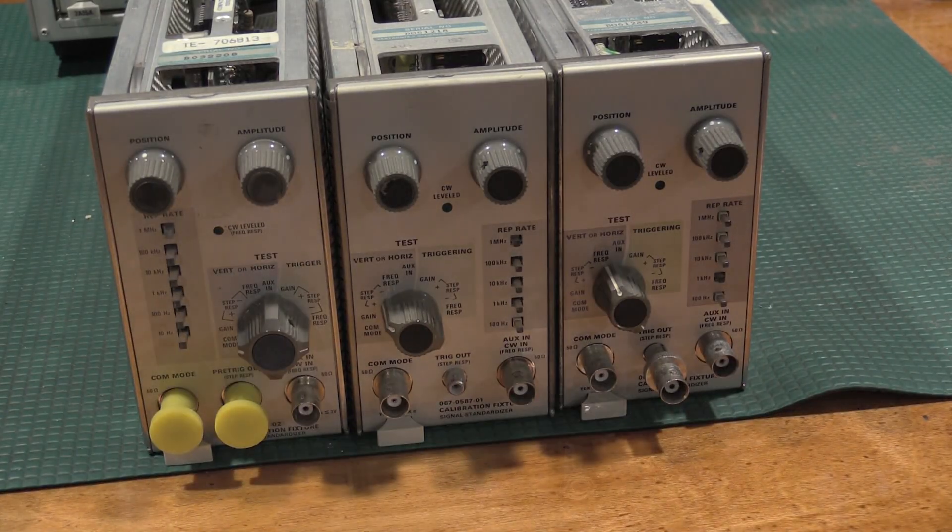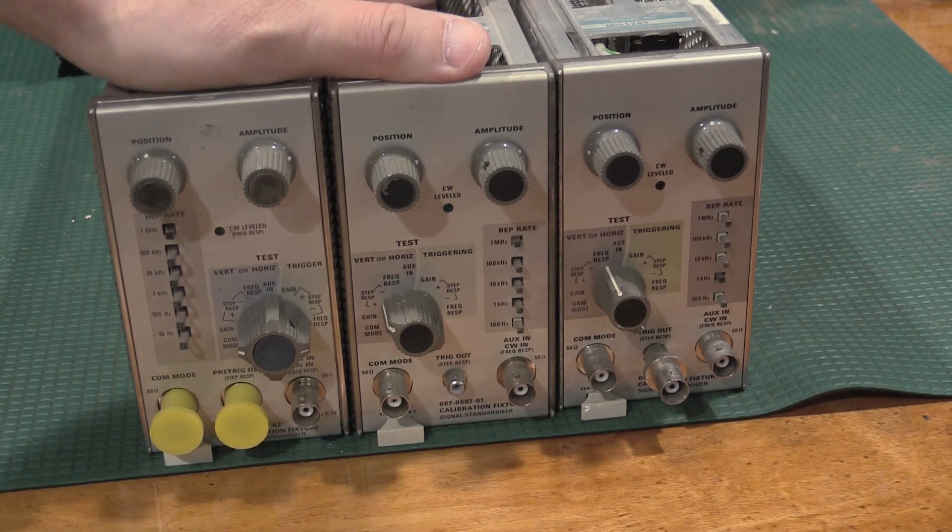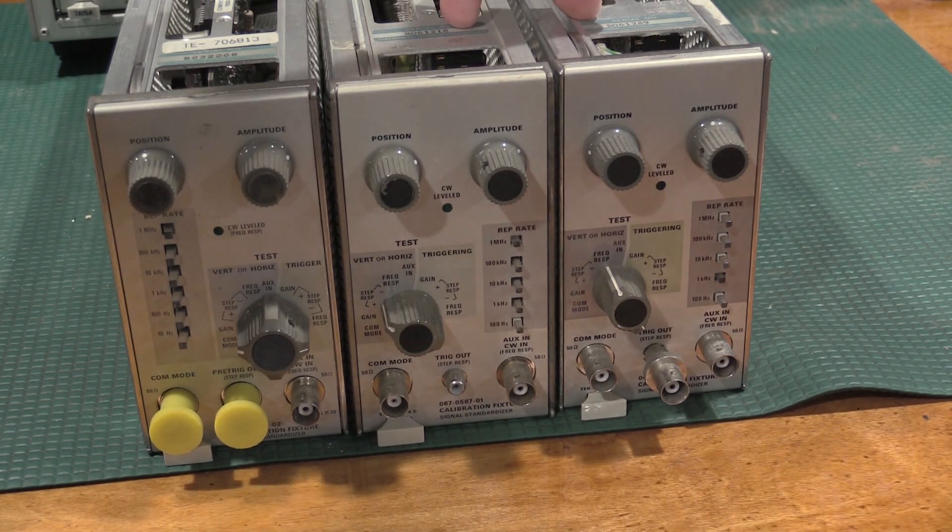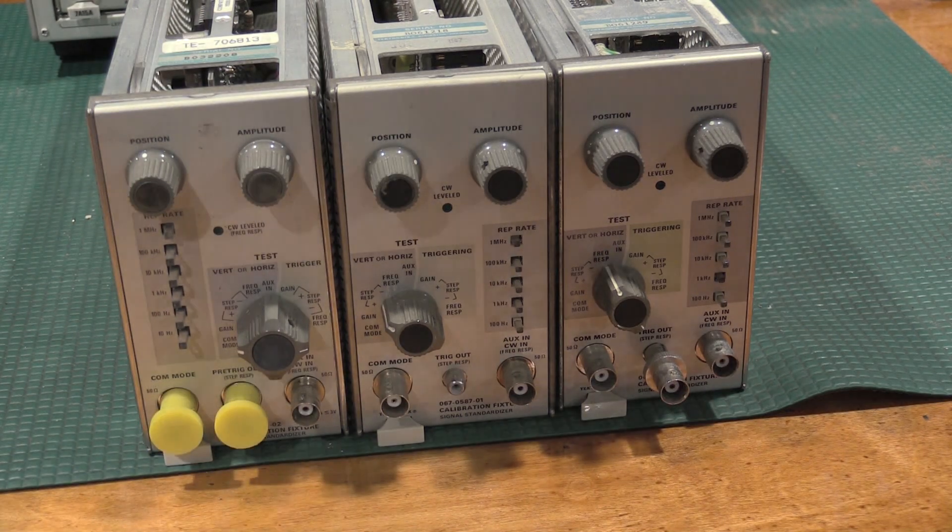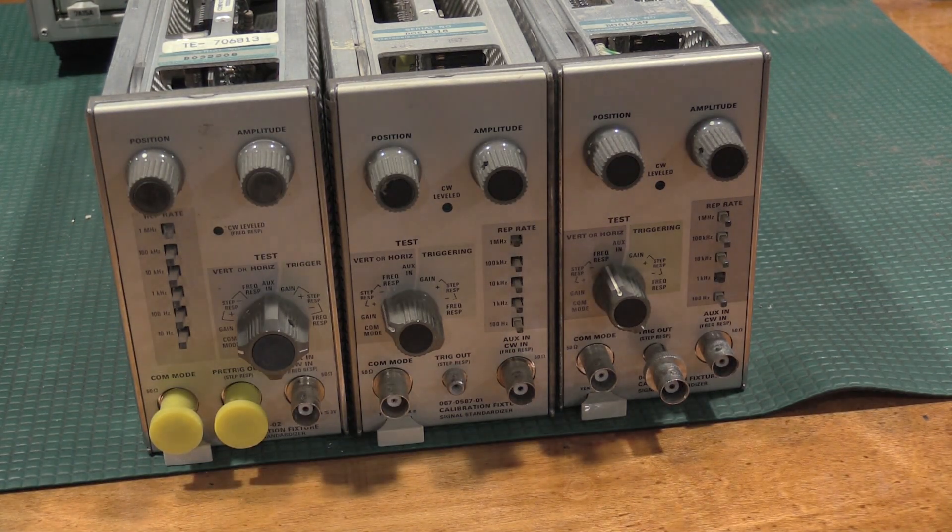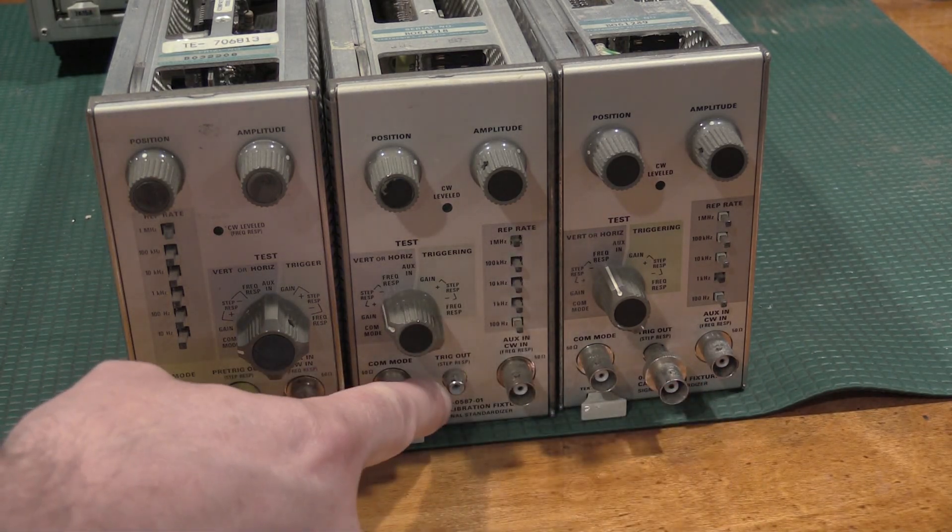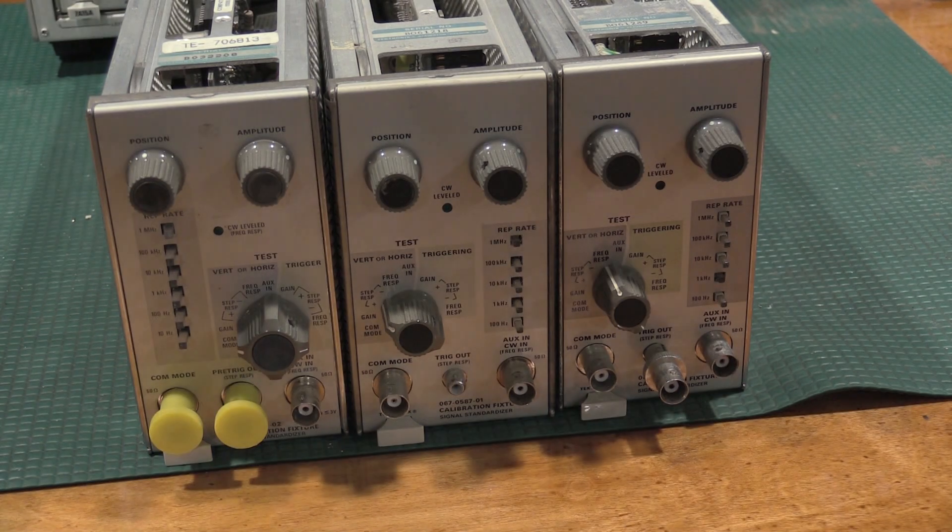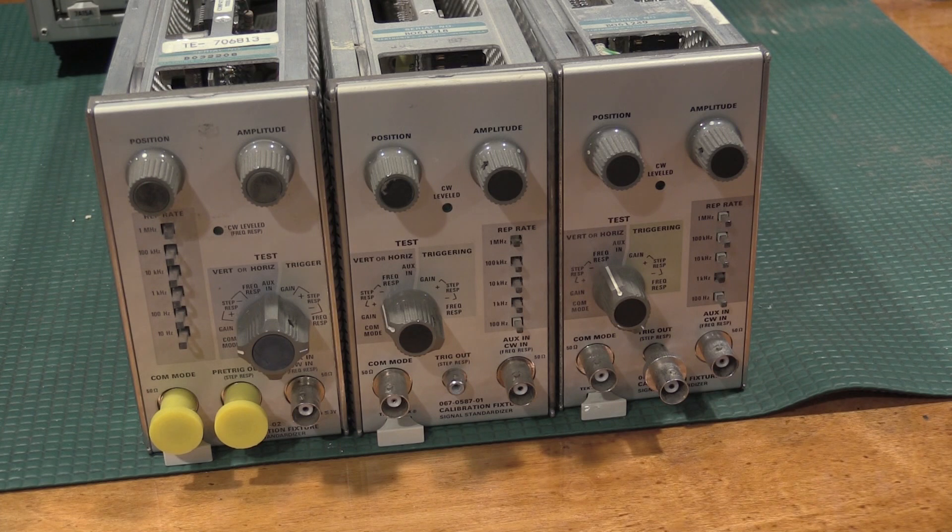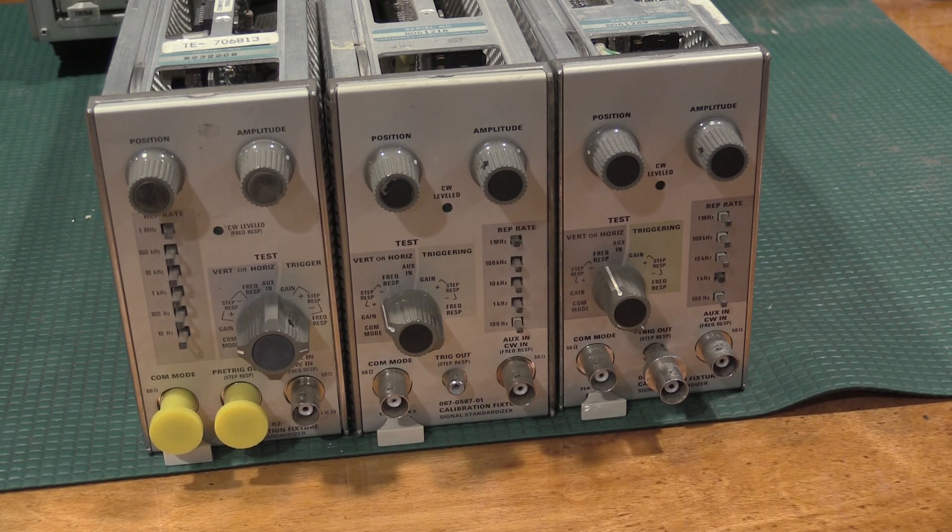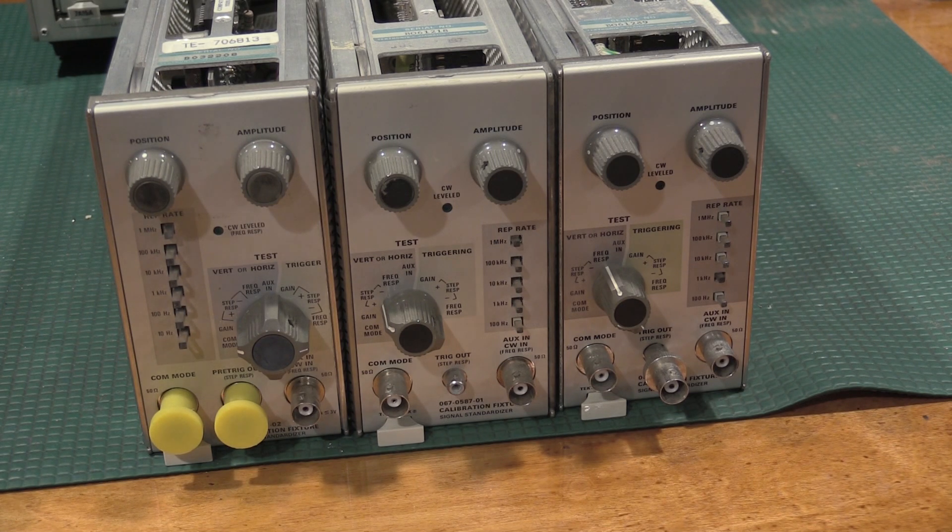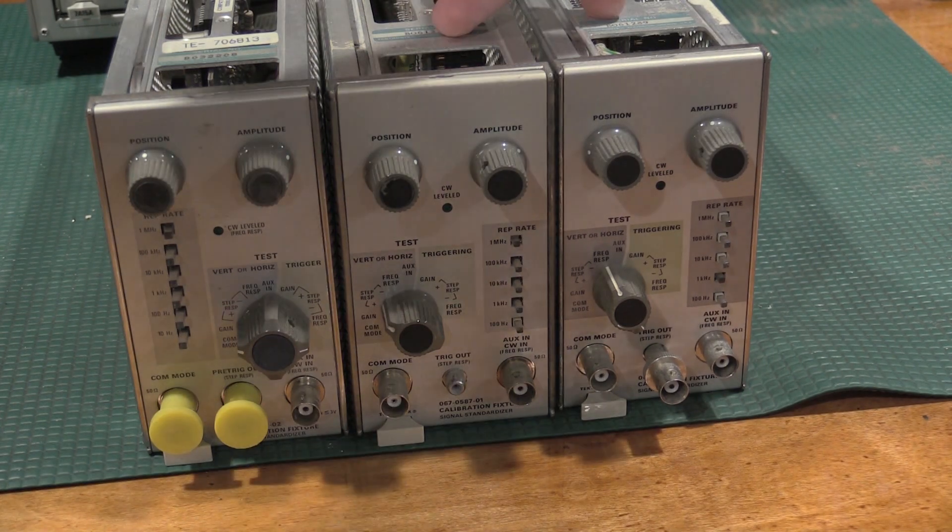So this is my complement in the lab of signal standardizers and plug-ins. I have two of the dash 01s and I have one of the dash 02s. Main difference between the two is speed. I did end up, there's a funny connector on one, so I ended up getting the connector. Now, the plug-in does a couple of features or does a couple of things that are important during the alignment and calibration process is it generates some very specific waveforms, fast edges, a couple of things like that. Helps out immensely with the geometry alignment with the tube, especially if you have two of them.